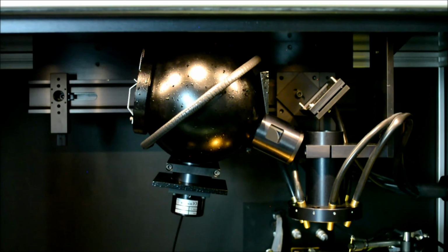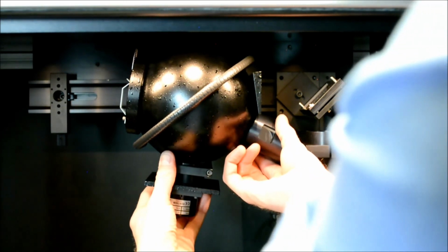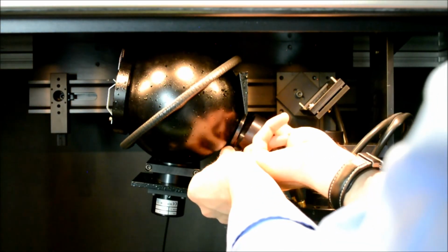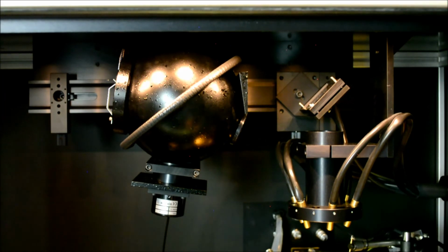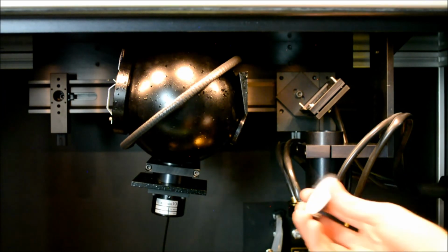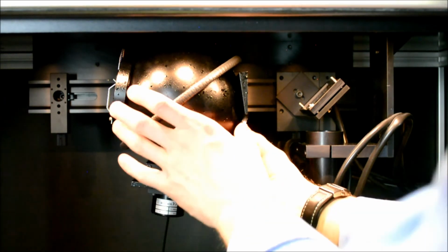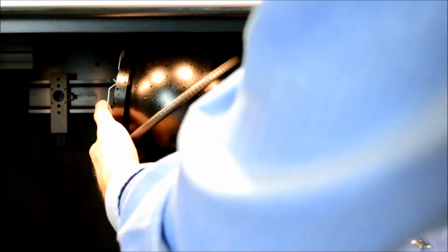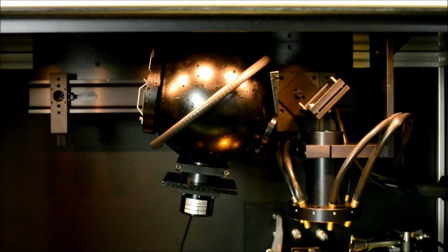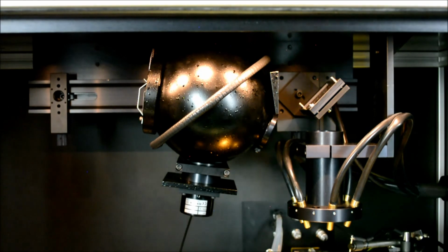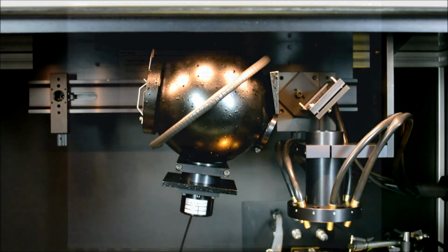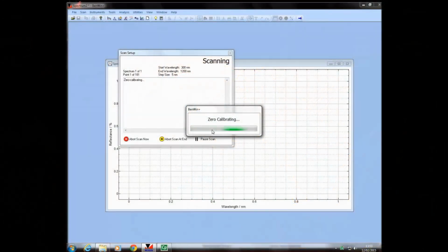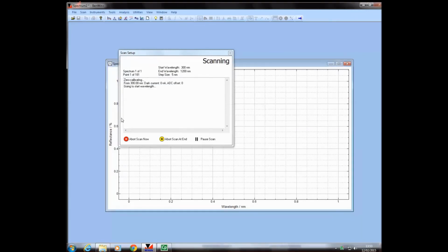And when you're happy with that, you can translate the sphere back, replace the specular reflectance port cover, replace the sphere to the right hand position, and perform the measurement of reflectance. We launch a new scan, seeing on the y-axis the reflectance being reported in units of percent.